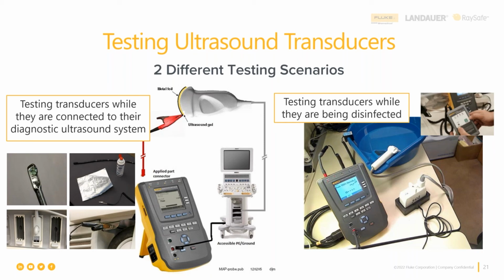Now, in the little insert picture in this slide, you'll see a different tester. This is called the ULT800. It is designed specifically for less technical people that work in central processing where this cleaning happens. Because there are no big graphic displays on the ULT800, it is simply a pass-fail device. It is also a battery-powered test instrument. So we run a mains on applied part test-ish, which means the battery is providing the push, but it's only got 12 volts. So even if the cleaning technician put their hands in the cleaning solution while we're running this test, they wouldn't be harmed. They might feel it, but they wouldn't be harmed. So that's why we produce this.